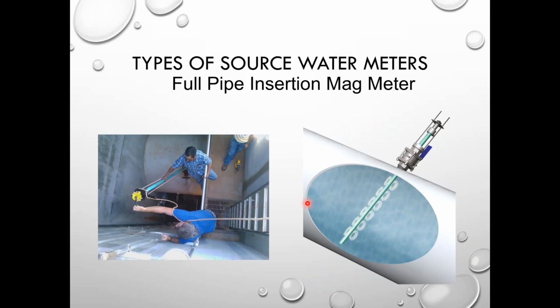Okay, next type of full pipe meters is an insertion meter. So we've got a mag insertion meter, which has a probe that goes down into the pipe. This one does not come with an area, right? It's going to use the area of the existing pipe. So when customers come and purchase an insertion meter, the number one mistake people make is not being able to identify the ID accurately. So we have devices that can go down into the pipe and measure the ID for the customer. So they need to know what the ID of that pipe is.